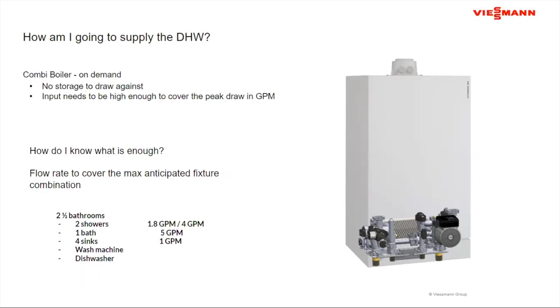Okay, so combi boiler, no storage to draw against. I need to provide the peak in gallons per minute. So the question is always right here: how much hot water is enough? How much hot water do I need? In reality, when I look at doing a combi boiler, I have to do an inventory of the fixtures in the house and find out what the peak water usage is going to be for those fixtures.